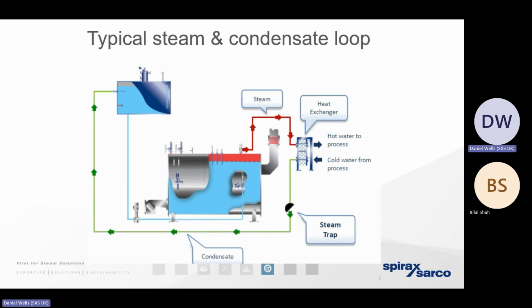So the space at the top of the boiler that's shown in red, that's the space that exists to allow that expansion to take place. Remember, this boiler is operating under pressure. I'm going to use the example of 10 bar gauge. The reality is, in industry, a typical horizontal fire tube boiler, that'll be working at pressures typically between 7 bar and 12 bar gauge pressure.